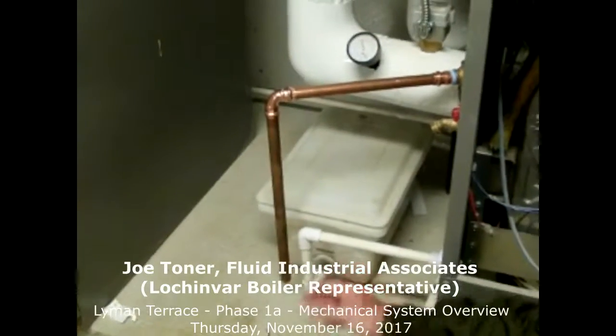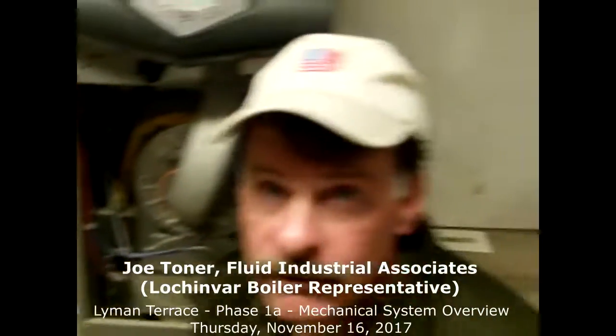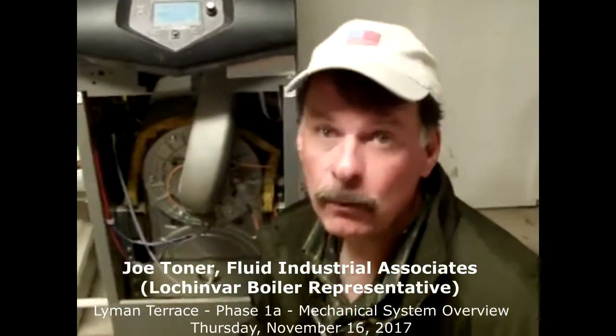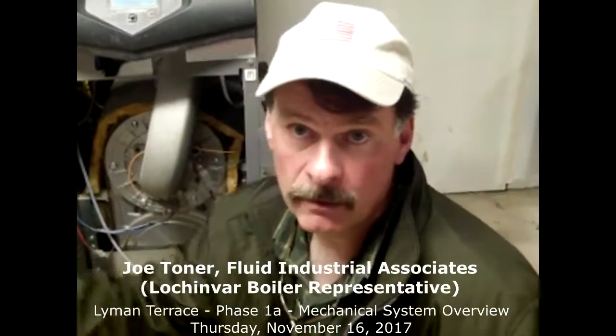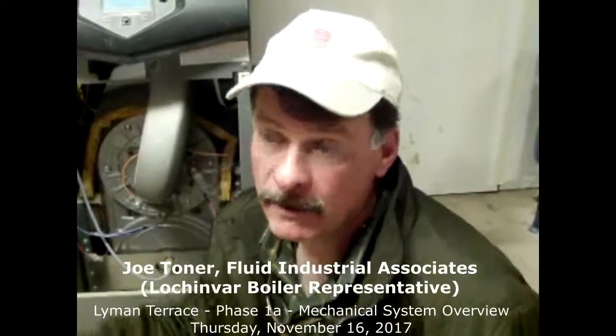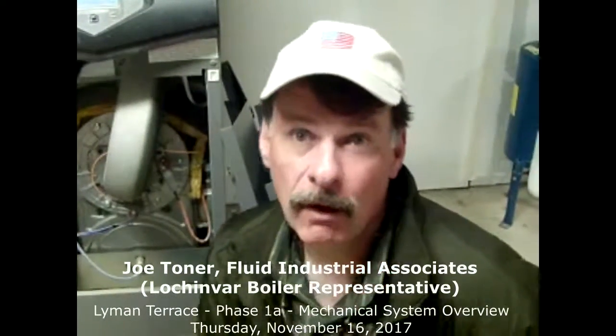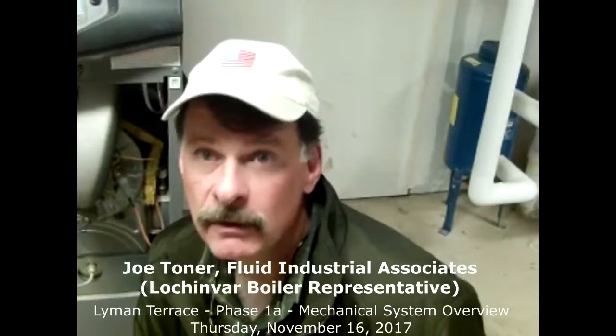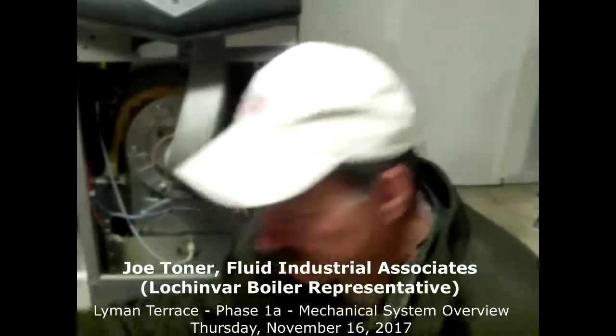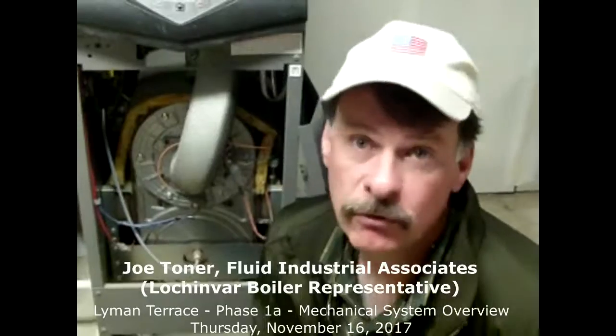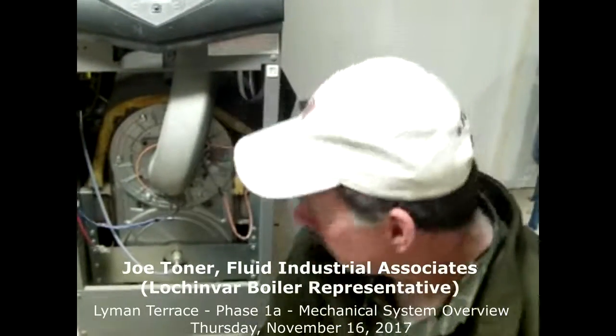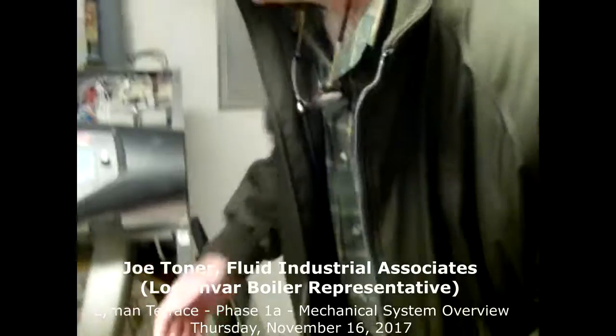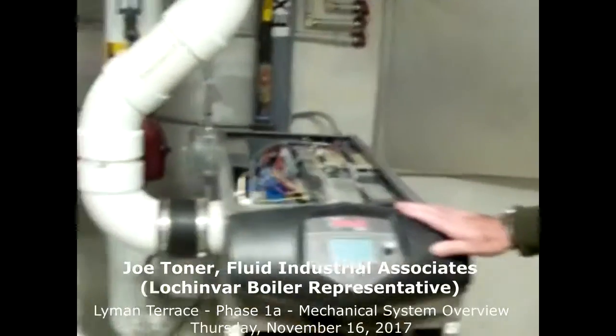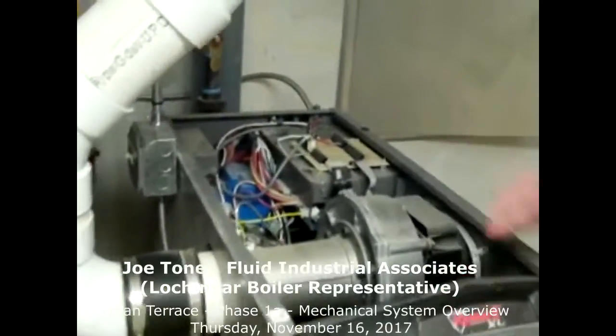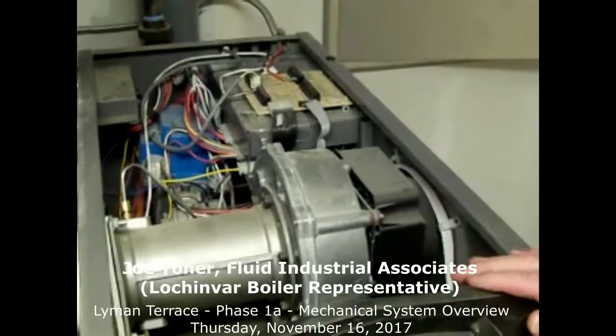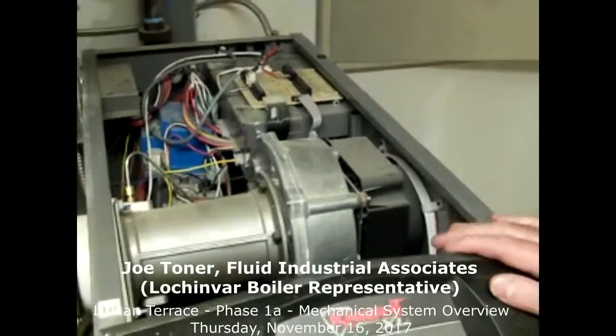Oh, okay, so it's sacrificial. It is sacrificial. It uses up. Yes, and the reason for it is in New England we have an older infrastructure system in terms of the pipes in the street, and they're cast iron, so if we're getting acidic water out there, we could harm those pipes. So that's kind of important as well. So it's just a visual inspection, and I think most hardware stores you can buy limestone, and it's just topping it off. And then other than that, you just want to inspect visually the wiring, the components, make sure nothing's loose, and really that's about it.